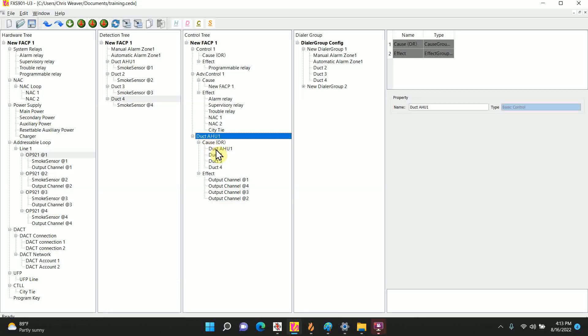Now we're left with the original control. If you look at the cause, I got all four duct detectors. It's an OR statement, so if this one goes off, or if this one goes off, or if this one, or this one, it activates this control. And the effect is all four duct detectors relay trip. So you just tell the guy who was ever hooking it up, just pick the closest or easiest duct detector to hook up to and hook up your relay to the shutdown. You don't need to hook up all four, just pick the closest, easiest one.